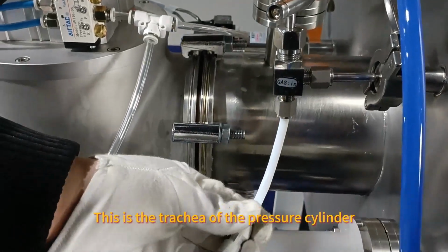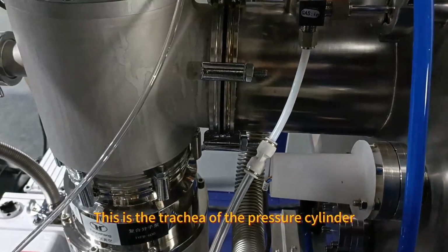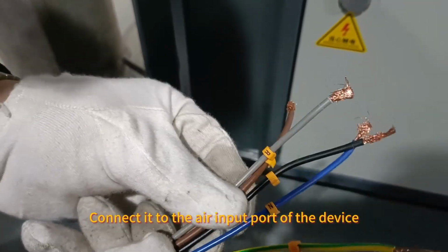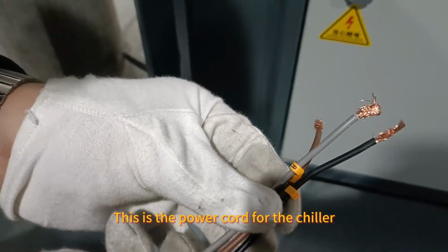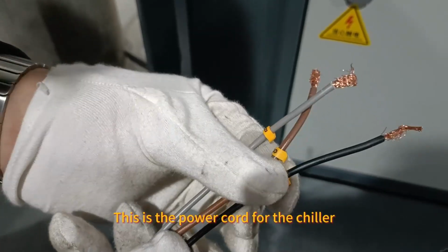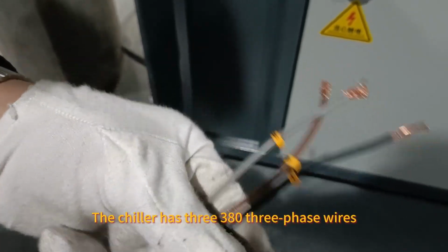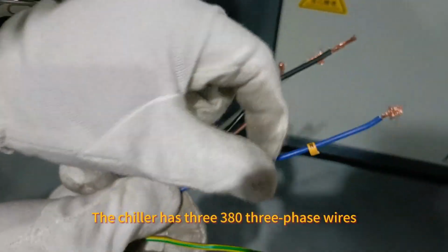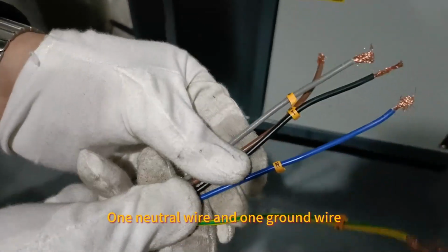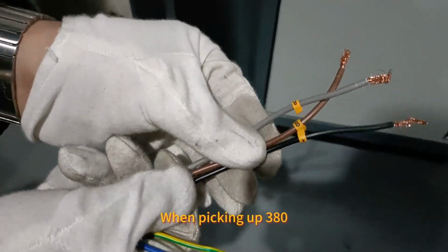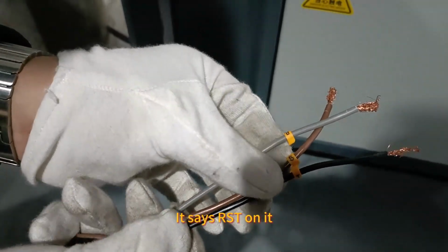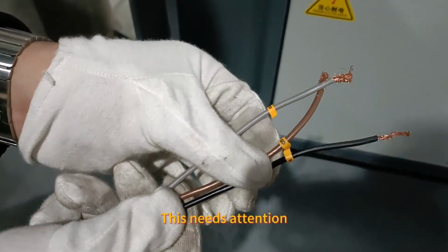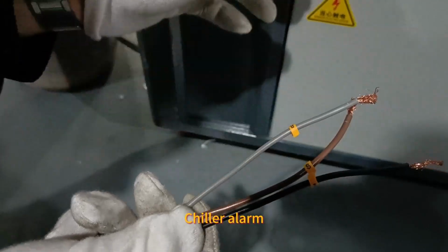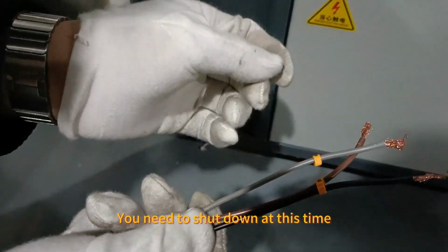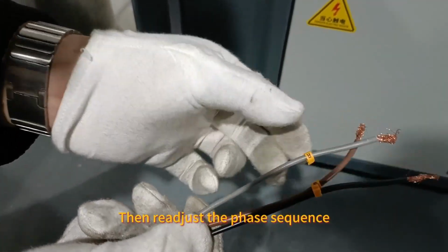This is the trachea of the pressure cylinder. Connect it to the air input port of the device. This is the power cord for the chiller. The chiller has 3 380 three-phase wires, 1 neutral wire and 1 ground wire. When connecting the 380, it says RST on it. This needs attention: if the chiller alarms, you need to shut down at this time, then readjust the phase sequence.